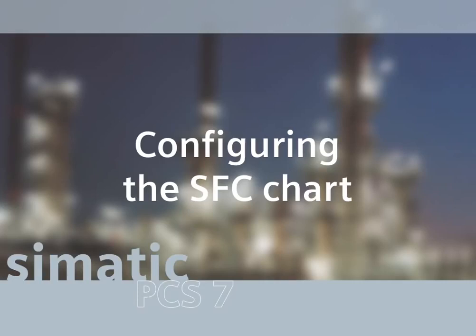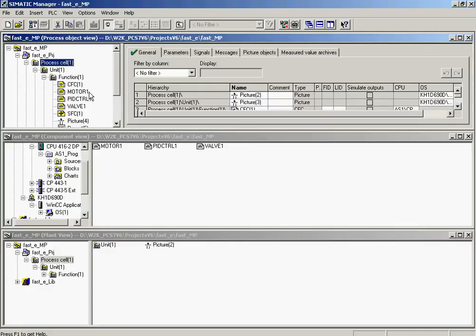Before the CFC charts are interconnected, an SFC chart must be created to control the sequential operation of the motor and valve, since this configuration logic must also be available for the second plant section. The SFC chart SFC1, created by the PCS7 wizard in the Function 1 folder of the FAST-E-PRJ project, is renamed and adapted for the simulation.